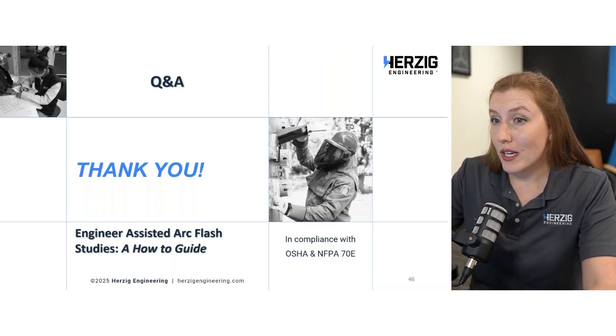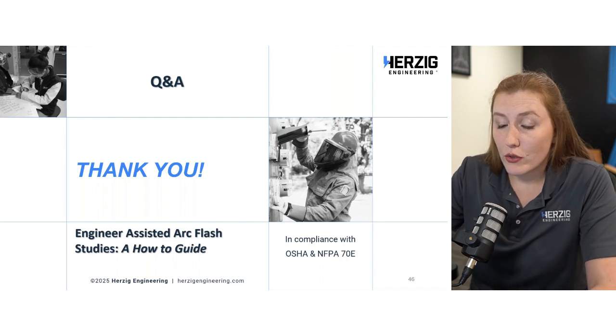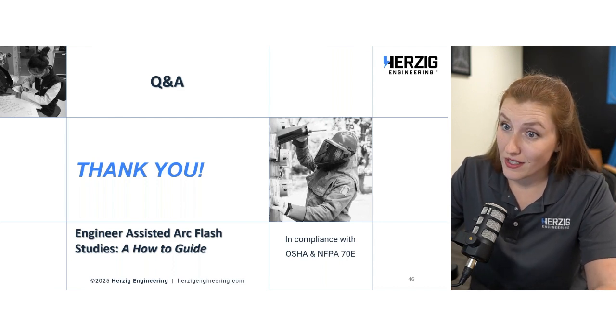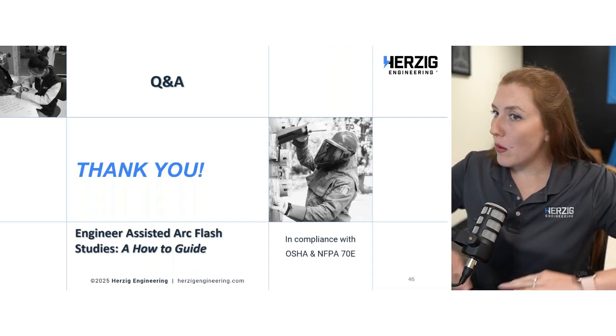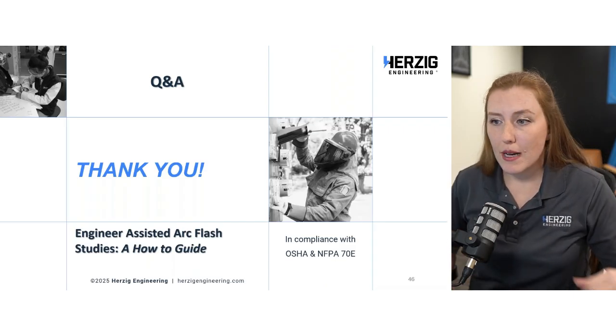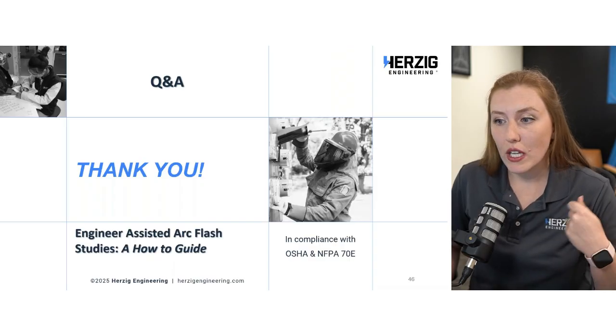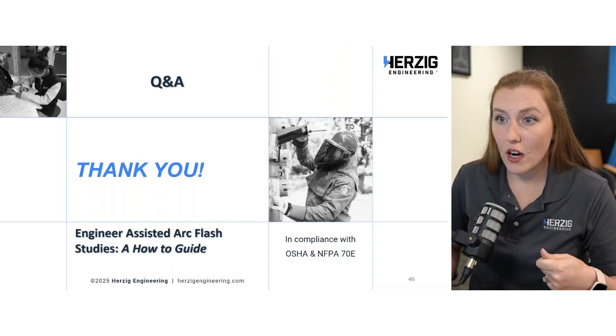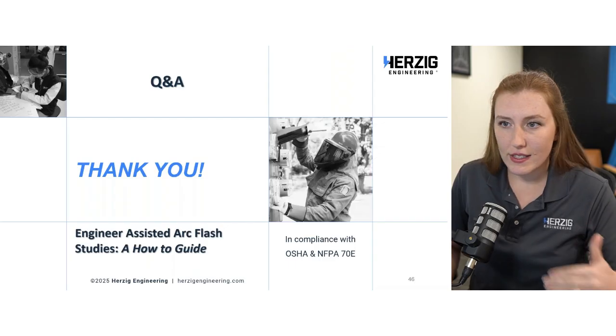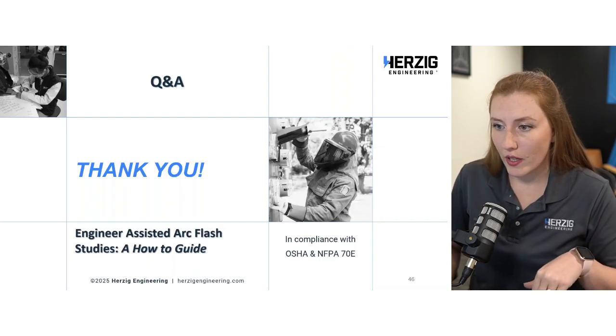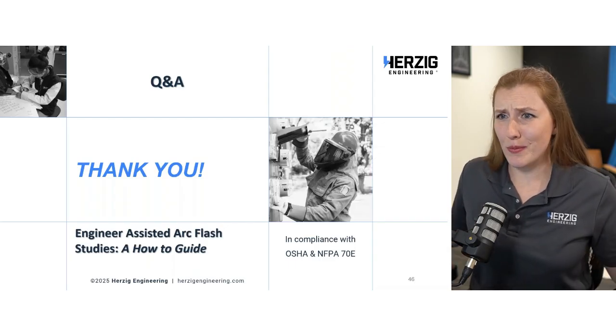So even just opening it up and looking at it, even if you're just going to get a voltage measurement, or troubleshooting, it is energized work. Bare minimum, you have to open it up to verify that it's off with your meter. Only qualified persons with proper protection are allowed to do that. You cannot skip an arc flash calculation just because you don't work energized. By the way, nobody should be working energized.